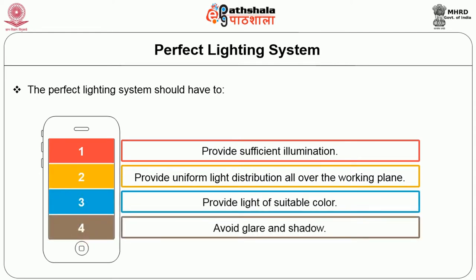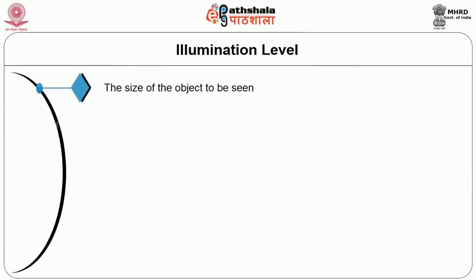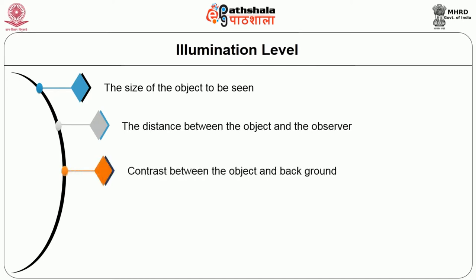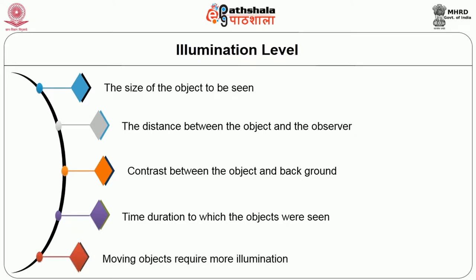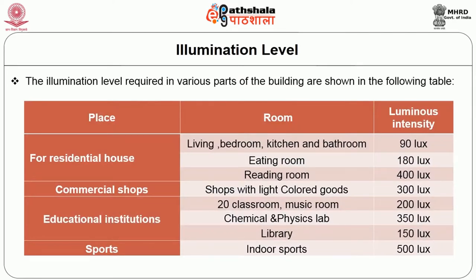The following factors are to be considered while designing a lighting scheme. Illumination level: for each type of work, there is a range of brightness which gives maximum output in terms of quality and quantity. The degree of illumination required depends on the size of the object to be seen, the distance between the object and the observer, contrast between the object and the background, the time duration for which objects are viewed, and whether objects are moving — moving objects require more illumination.